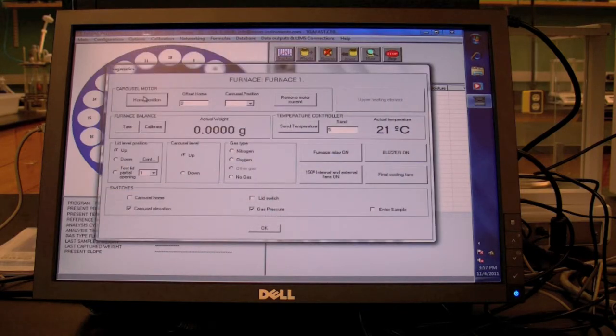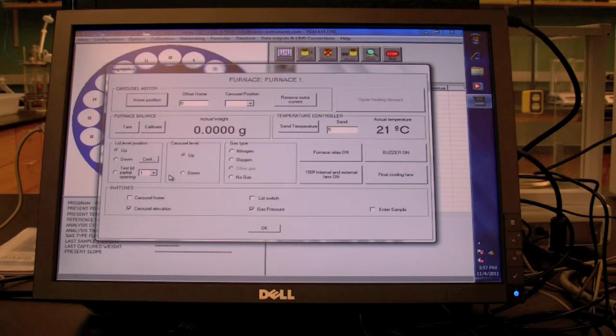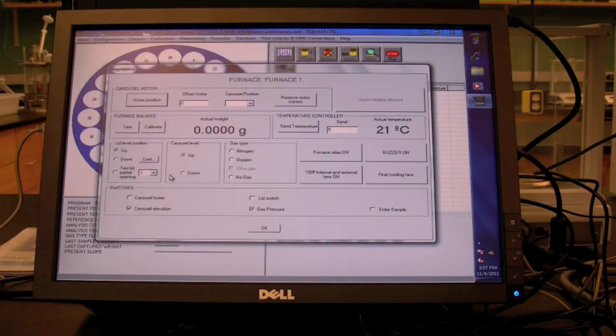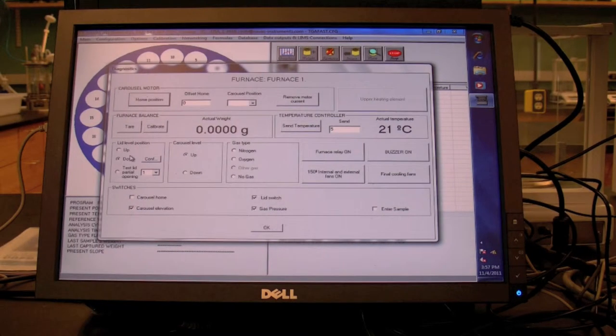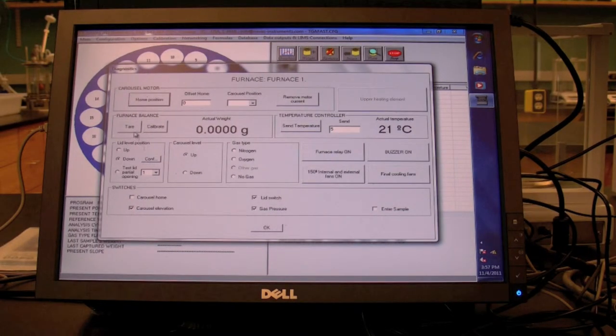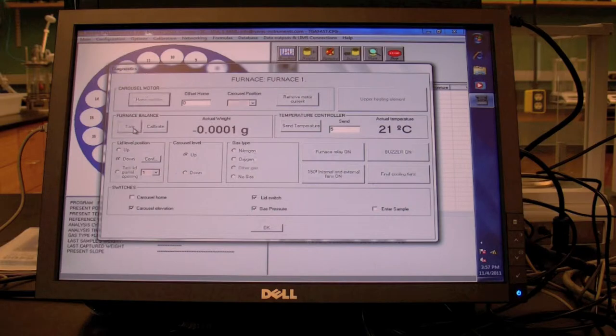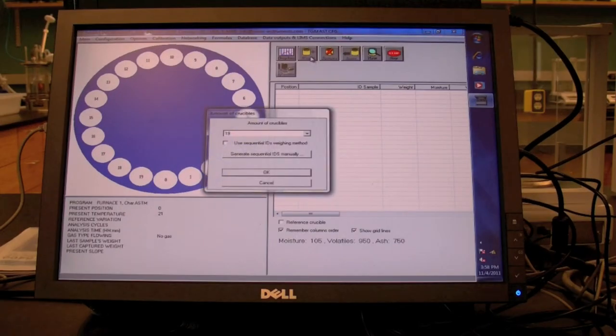The diagnostics window will pop up. Without any crucibles in the carousel, click down. Once the lid is closed, click the Tare button to zero out the scale. Next, click on the wait icon.